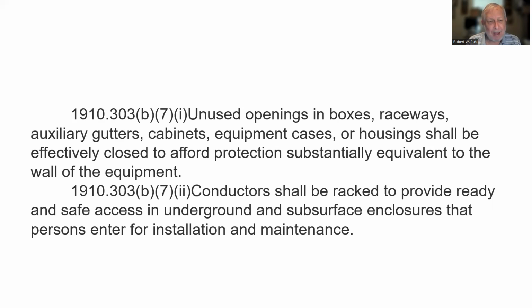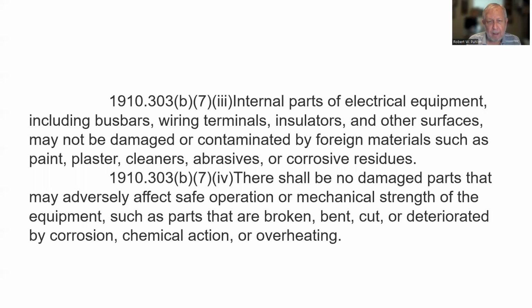Conductors shall be racked to provide ready and safe access in underground and subsurface enclosures that persons enter for installation and maintenance. Internal parts of electrical equipment, including bus bars, wiring terminals, insulators, and other surfaces may not be damaged or contaminated by foreign materials such as paint, plaster, cleaners, abrasives, or corrosive residues. There should be no damaged parts that may adversely affect safe operation or mechanical strength of the equipment, such as parts that are broken, bent, cut, or deteriorated by corrosion, chemical action, or overheating.